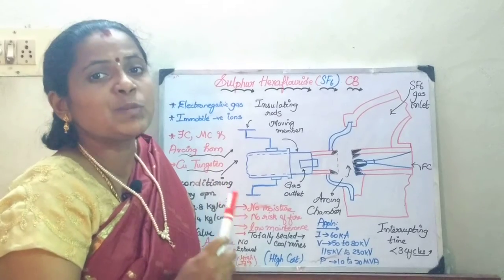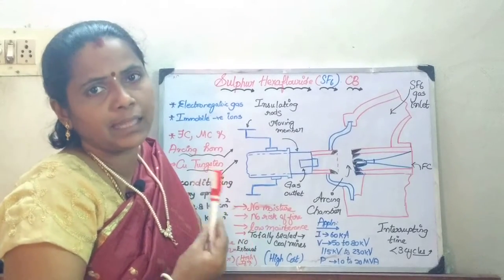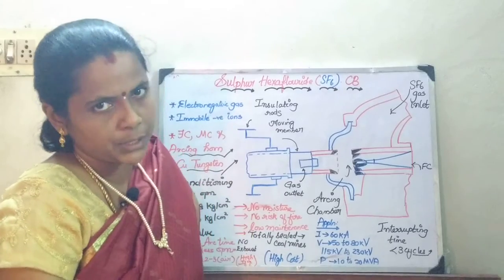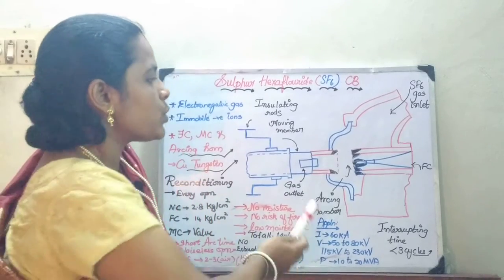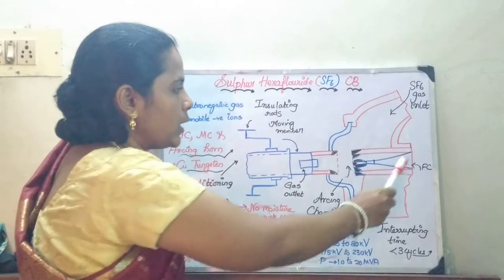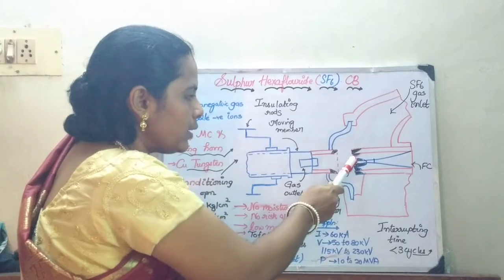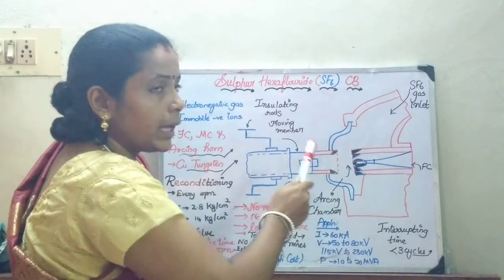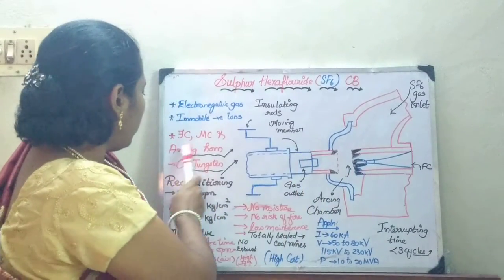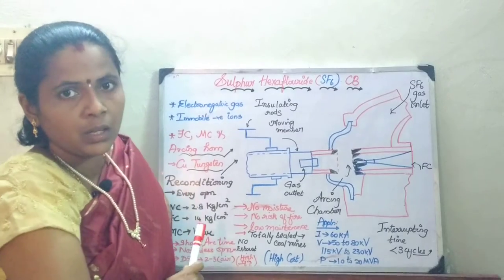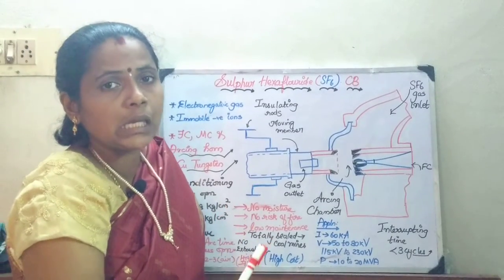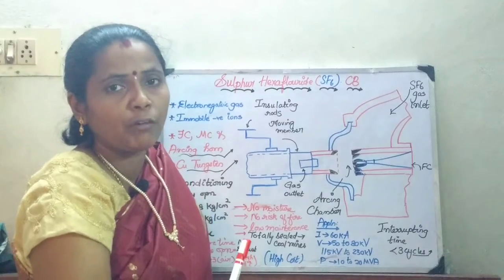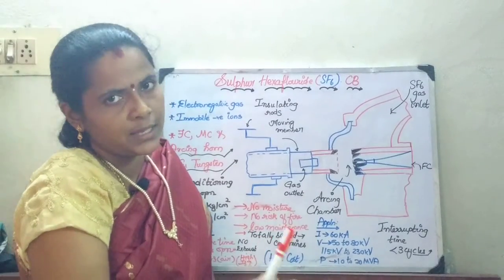The arcing horn is used to split the arcs and thereby extinguish the arc at a faster rate. The two special features are: one is the arcing horn, and another is that the fixed and moving contacts along with the arcing horn are coated with copper tungsten, so that it avoids the easy burning of the fixed and moving contacts whenever a fault is trapped.